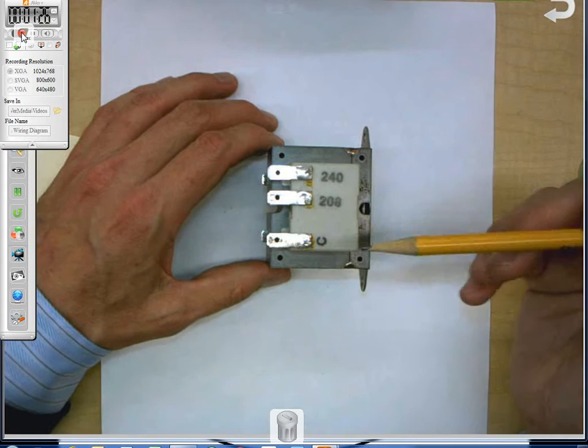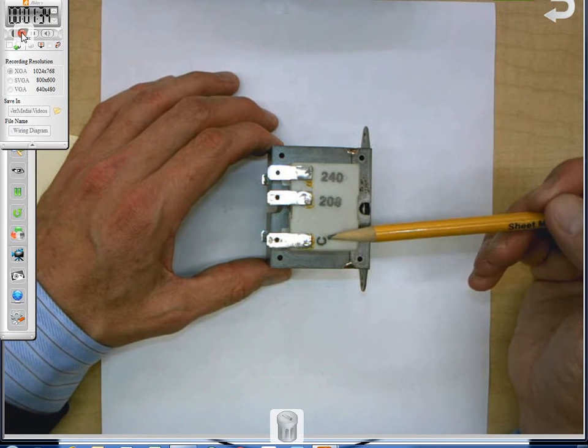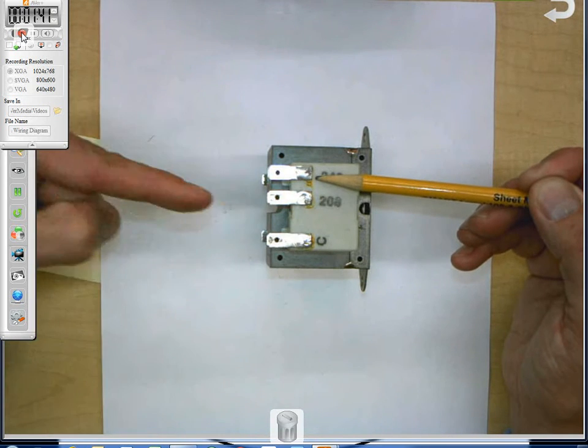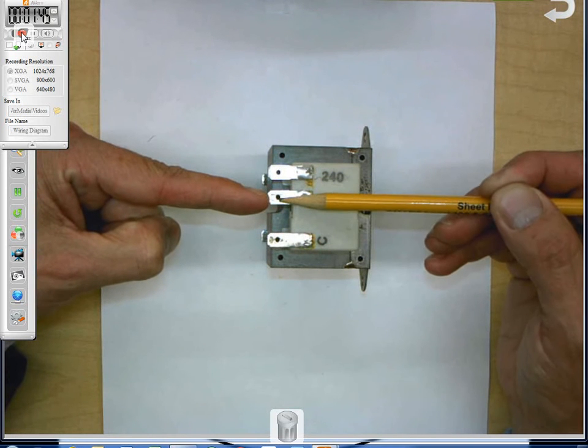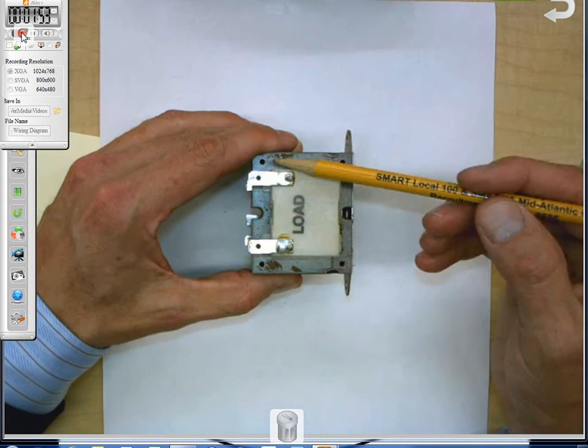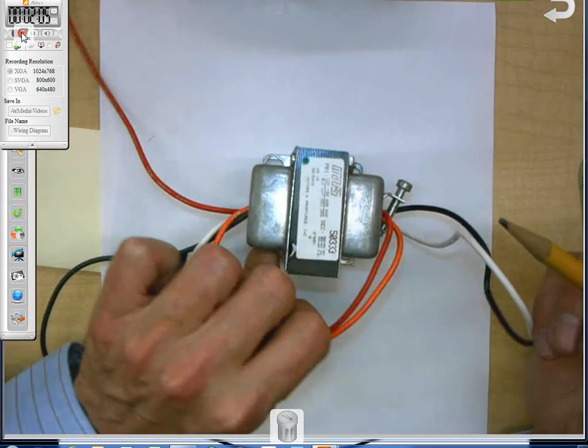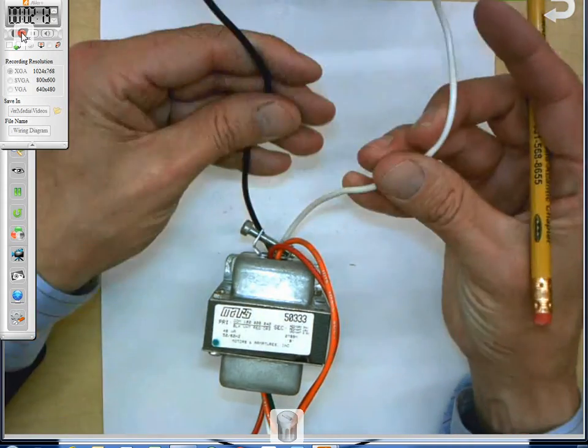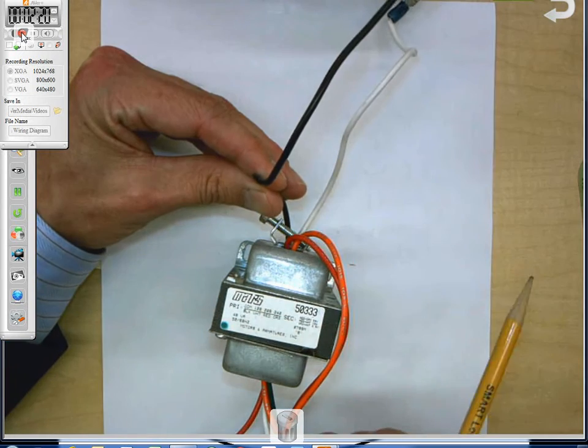Now yours should have looked like this for this particular project, where it only had two wires per primary, black and white. What does that mean? 120 volt, and then 24 volts secondary coming out. Now remember, all this is, is an iron bar with wires wrapped around it, connected to another iron bar with either less or more number of wraps wrapped around it. That iron bar transfers the power by induction from this side of the voltage of 120 volts to this side. And if it has less wraps, the voltage will drop down.